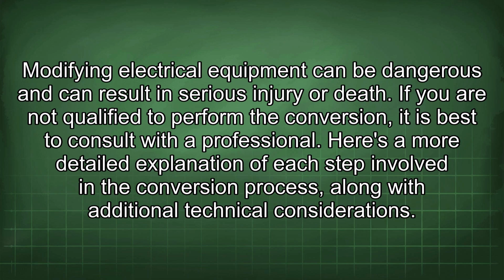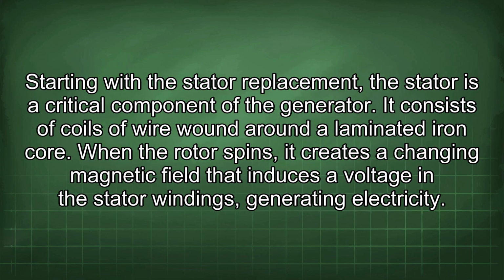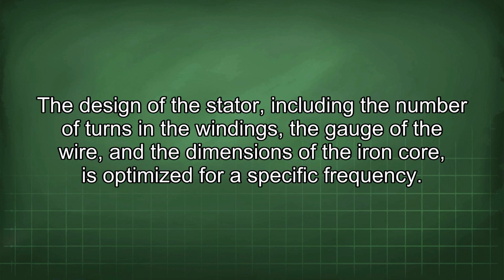Here's a more detailed explanation of each step involved in the conversion process, along with additional technical considerations. Starting with the stator replacement, the stator is a critical component of the generator. It consists of coils of wire wound around a laminated iron core. When the rotor spins, it creates a change in magnetic field that induces a voltage in the stator windings, generating electricity. The design of the stator, including the number of turns in the windings, the gauge of the wire, and the dimensions of the iron core, is optimized for a specific frequency.